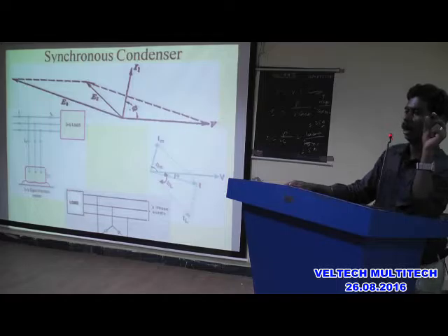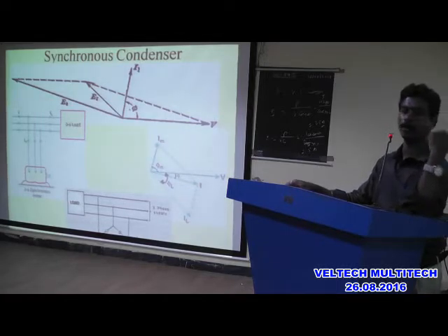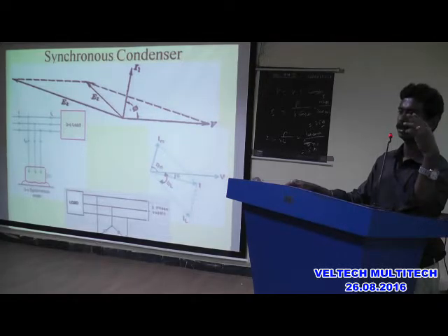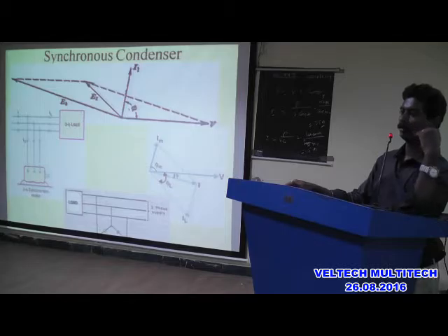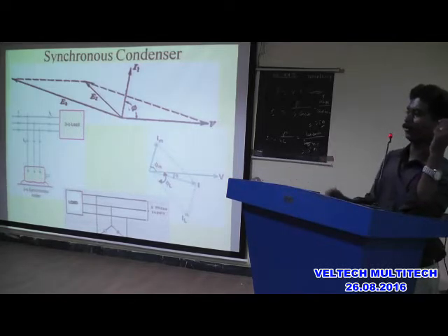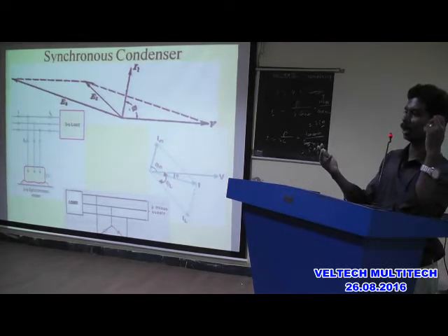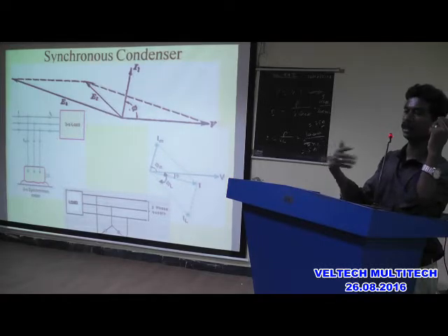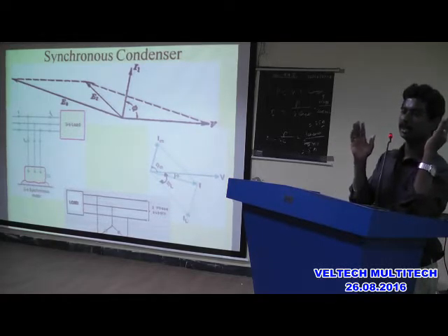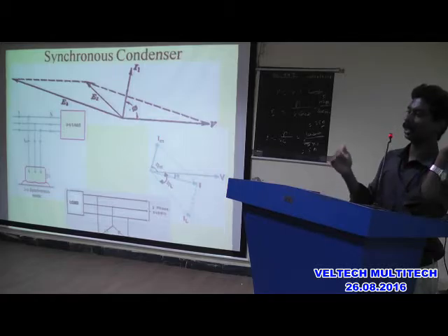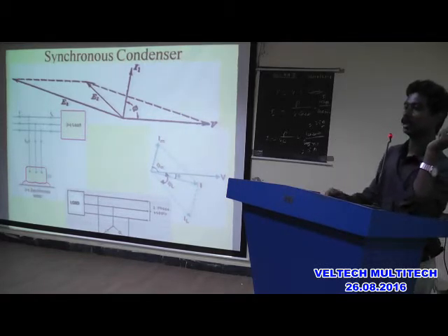So if you operate any synchronous motor in over excited condition, that will act as a synchronous condenser. So what is the function of a condenser? Condenser means capacitor. You use it to improve the power factor, and like that the synchronous motor is going to act as a synchronous condenser. A condenser is a static piece of apparatus, the synchronous motor is a rotating machine. So that is why this is called a synchronous condenser.